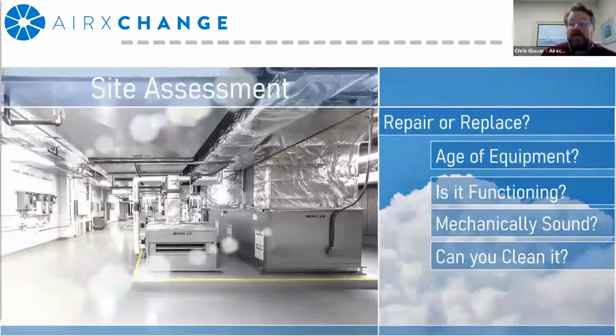Okay, so how do you assess what needs to be done to the device? Now, some of this may seem kind of trivial, but I just like to point it out. The first step is to identify, you should be asking, what's the relative age of the equipment? A properly maintained energy recovery component should have a lifespan of about 15 to 20 years. So if this device has never been maintained over that course of operation, it could be substantially less than that, depending upon what it's been exposed to.